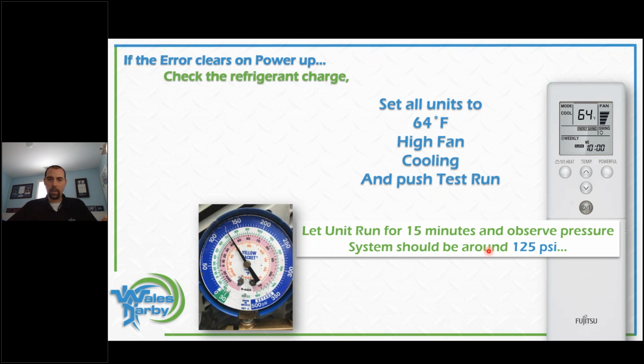And when you start to hear that and see that operation, you know right away we got a refrigerant issue. We got to now evacuate the system, pull everything out, pressure test it, find the leak, and repair it. The other way we can check refrigerant charge too, if the system's been off for a little while, take a look at your gauge, hook it up, take a look at your pressure.